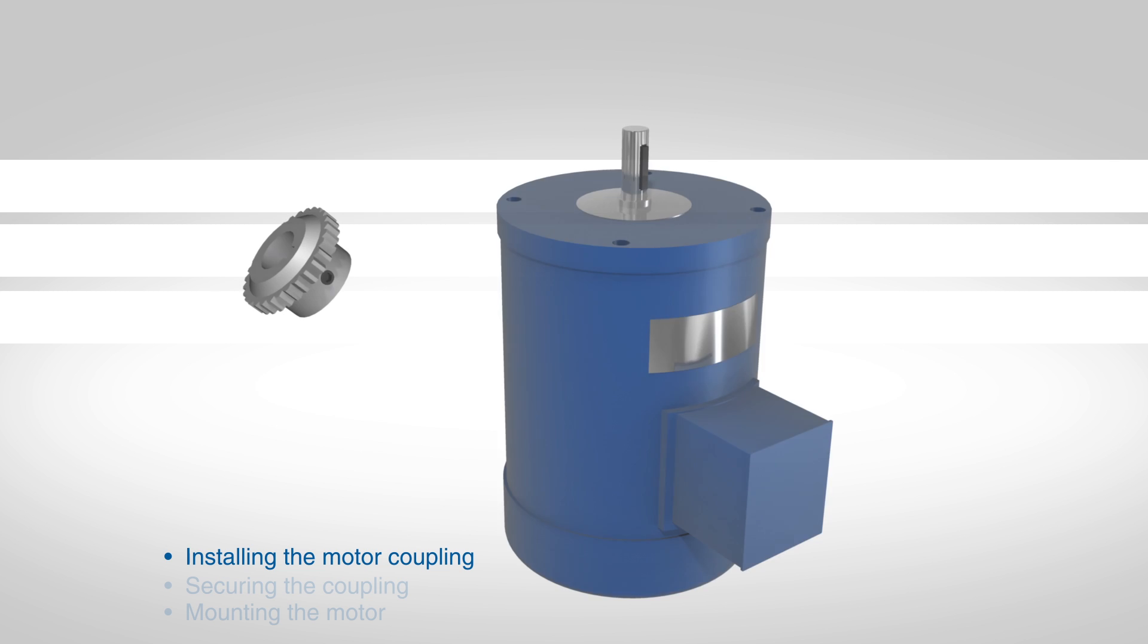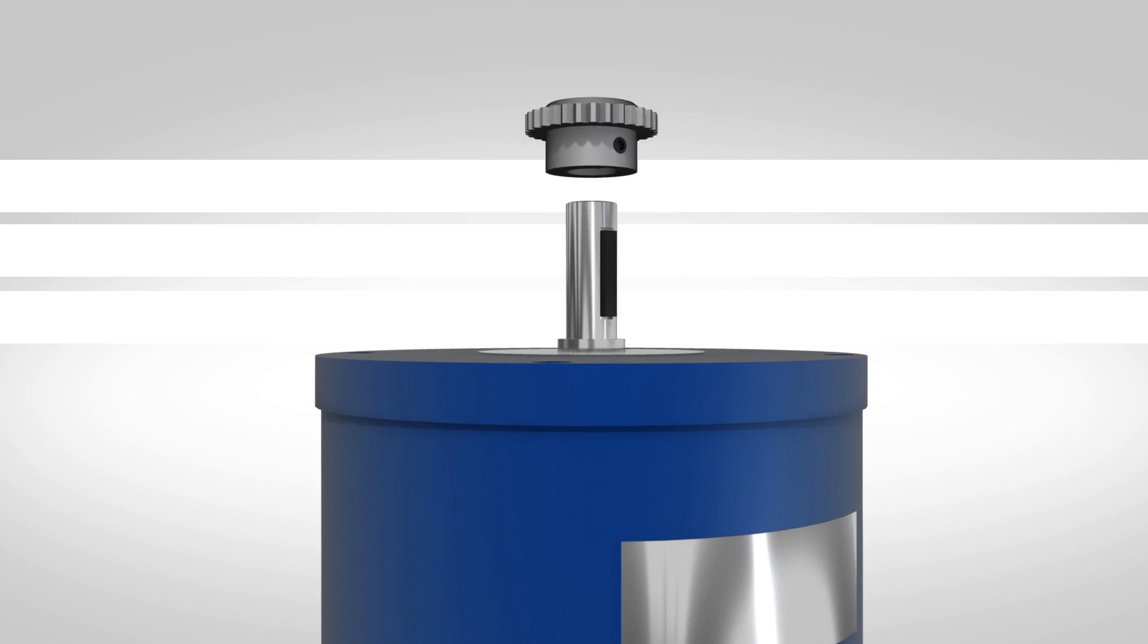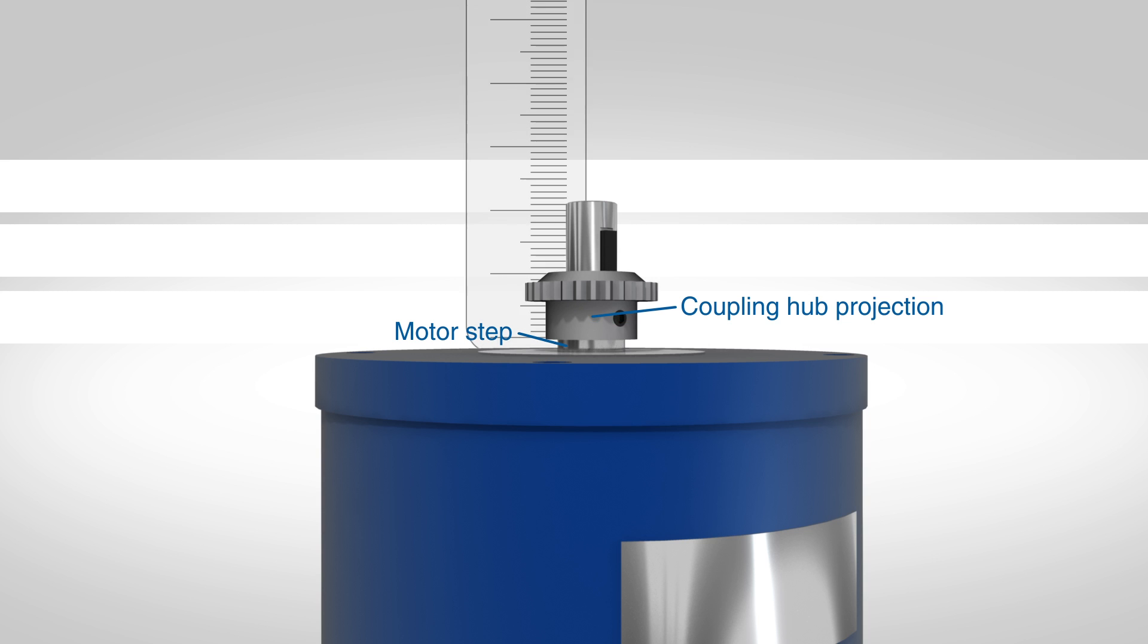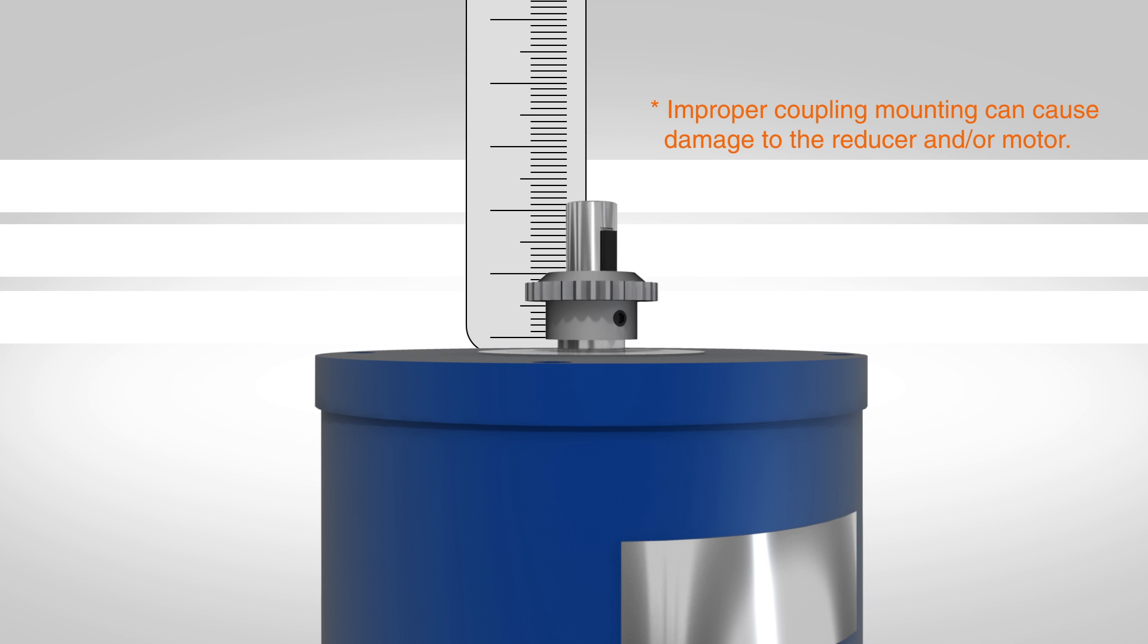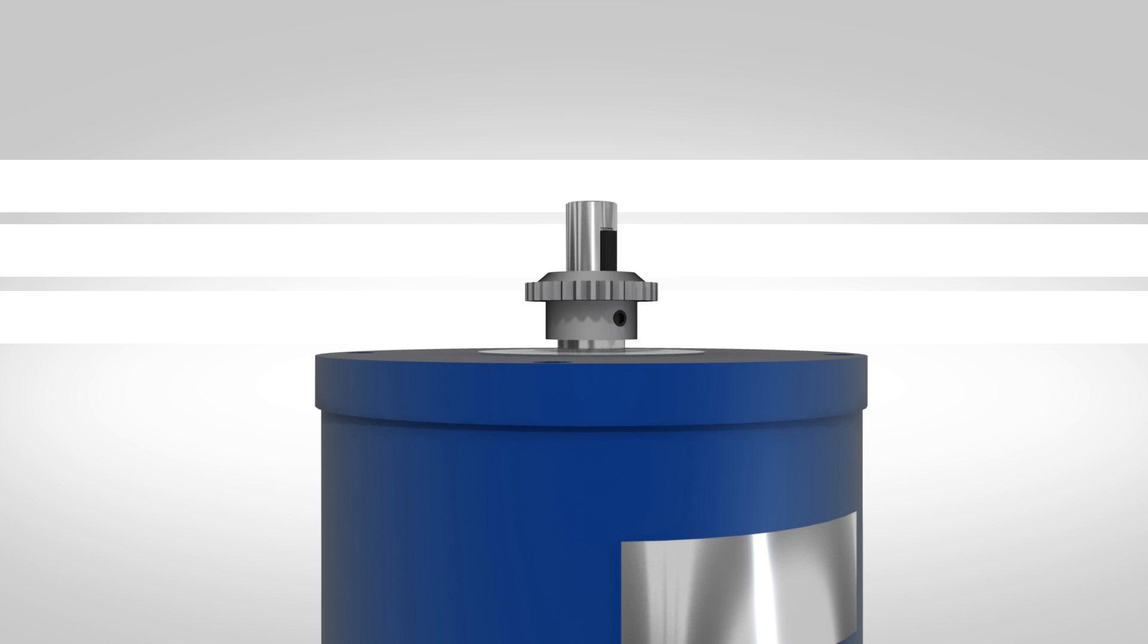Slide the motor coupling onto the shaft to ensure it is the correct size. Mount the coupling with the hub projection toward the step, or shoulder, of the motor. The coupling must be located correctly on the shaft. Failure to correctly locate the coupling on the motor shaft may cause thrust loads, which can cause premature failure of either the motor bearings or motor adapter bearings.